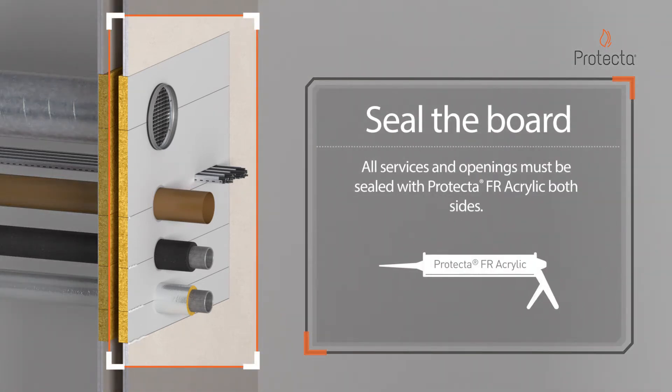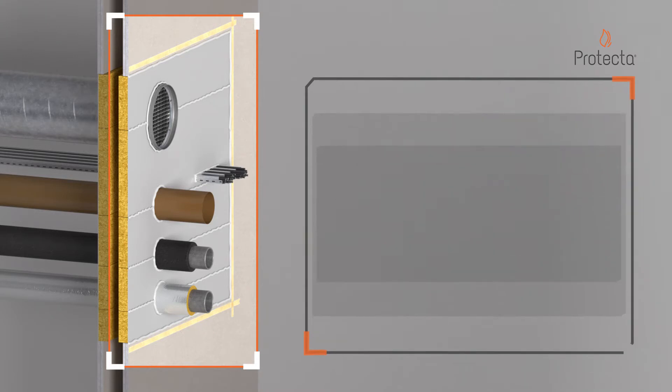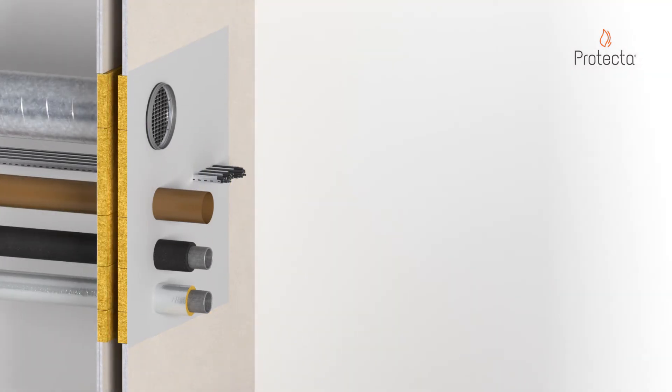All services and openings must be sealed with Protecta FR Acrylic on both sides. Use a trowel or wet brush to smoothen the seals of Protecta FR Acrylic for a neat finish and to ensure a smoke-tight seal.